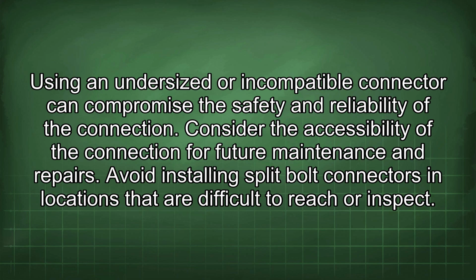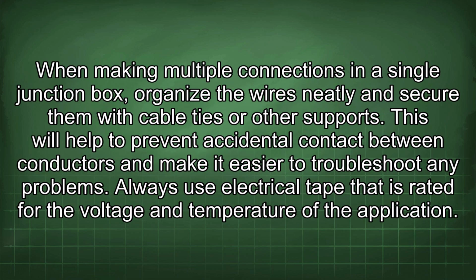Consider the accessibility of the connection for future maintenance and repairs. Avoid installing split bolt connectors in locations that are difficult to reach or inspect. When making multiple connections in a single junction box, organize the wires neatly and secure them with cable ties or other supports. This will help to prevent accidental contact between conductors and make it easier to troubleshoot any problems.